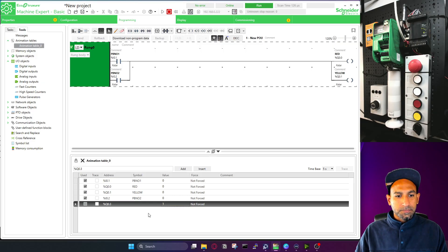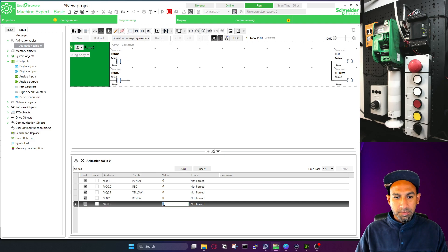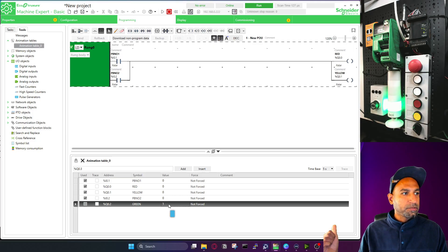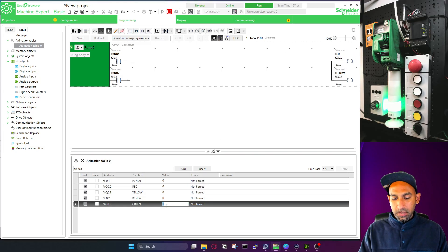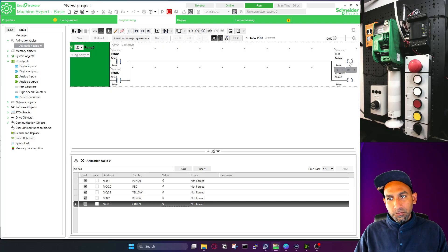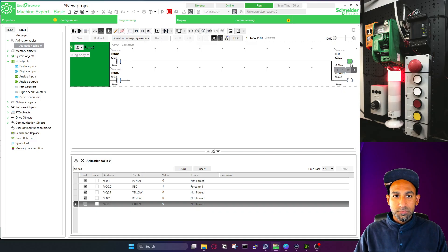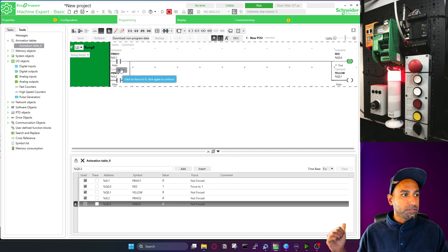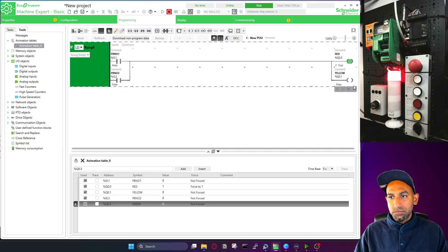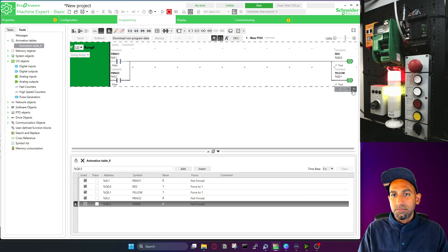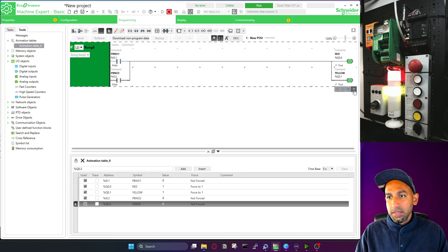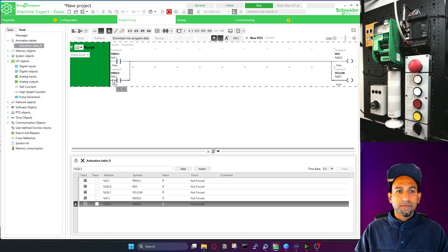If I make it 1 it should normally turn on my output. Q0.2 is connected to my lamp — Green 1. If I make it 1, you can see my lamp is on on my trainer, because I'm not using this output in my program and I can write the value. Otherwise I can force it — force my output to be 1 — and it will not depend on the logic. You can see my output is on and it's showing force to 1. Use force only when necessary, such as checking I/O status. But don't force it if you don't know what you're doing. Just remove the forces when done.